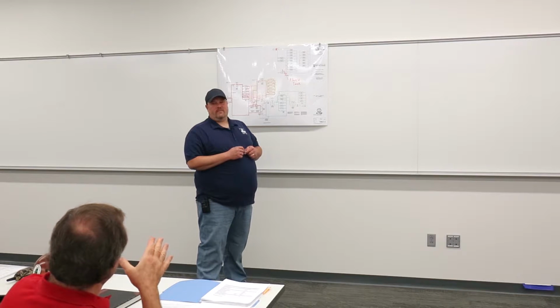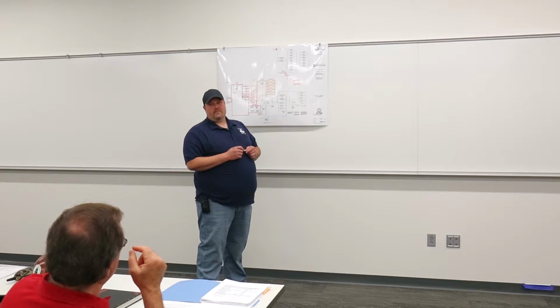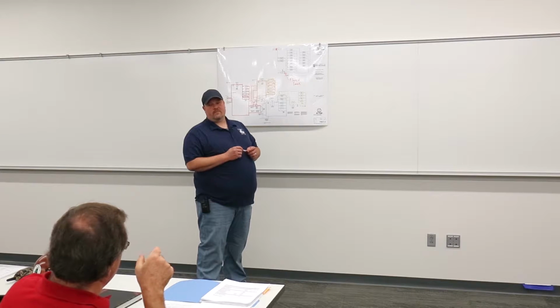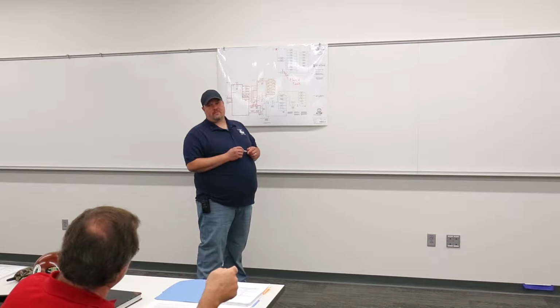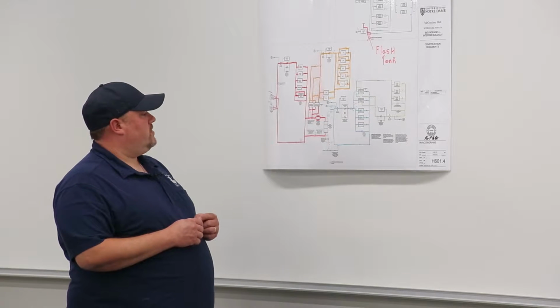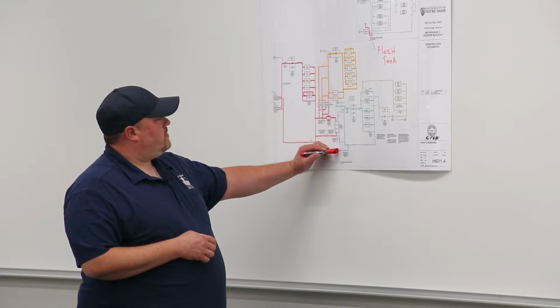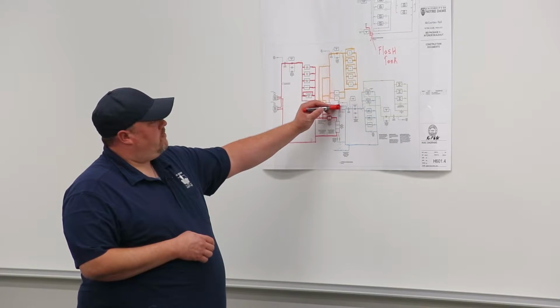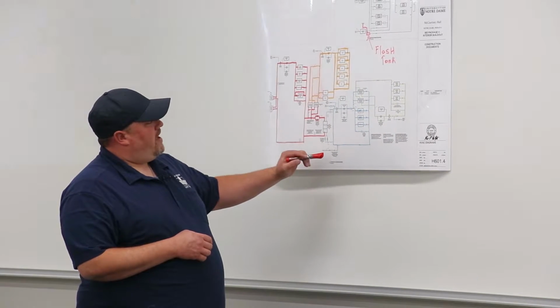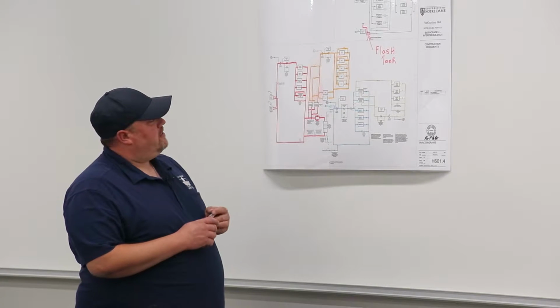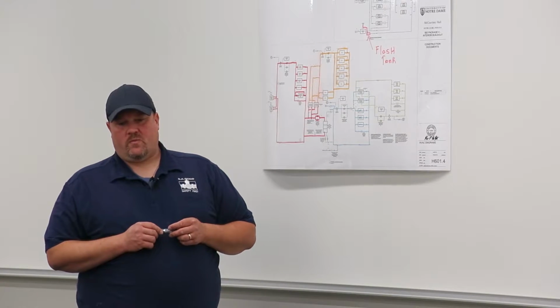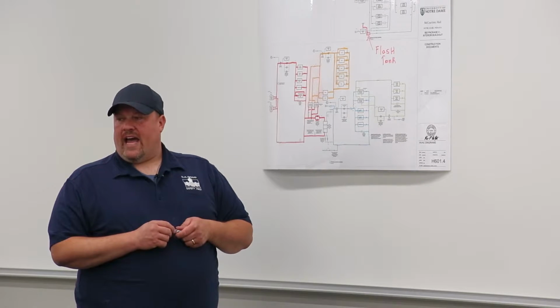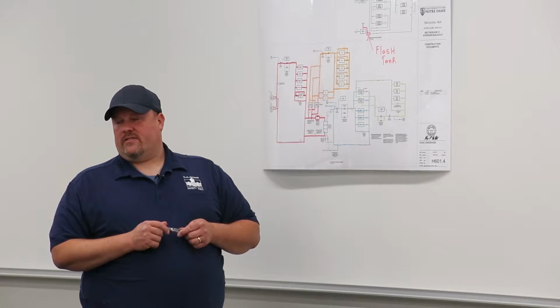Okay. Just while you're on that subject, with chilled water that's buried, there's a set of valves somewhere out at the mains that are like a yard valve, and then there's also valves inside the building? Yes, with the chilled water system, we have valves right inside the building immediately as they come in the building. We've got 2 valves. But they also have valves buried outside with curb boxes or access to be able to shut them out in the yard, yes.